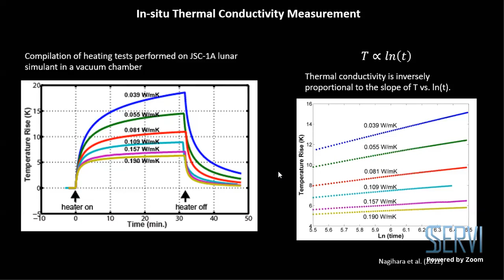As a summary, Lister is a compact, modular heat flow instrument that can be accommodated onto landers of various configurations. It will penetrate 2 to 3 meters into the lunar regolith and measure temperature and thermal conductivity every half meter depth interval. The heat flow is obtained as the product of the thermal gradient and the thermal conductivity. It completes all the necessary measurements within 1 Earth day, and it is destined to fly on one of the CLPS missions scheduled for 2022. Thank you for listening.